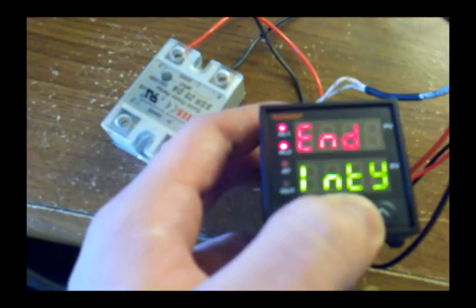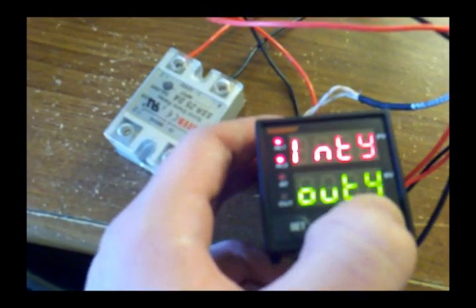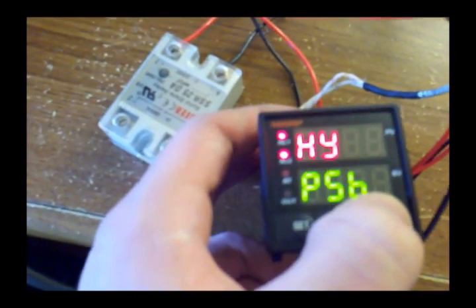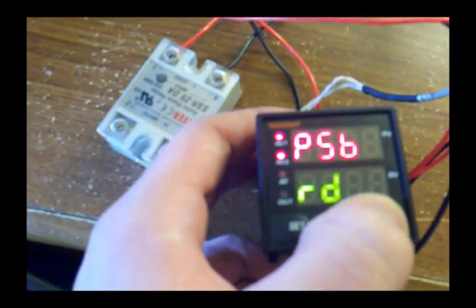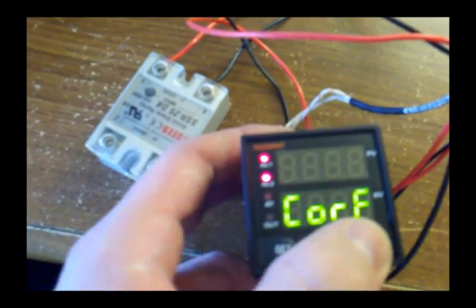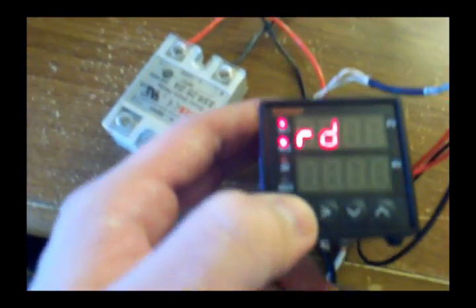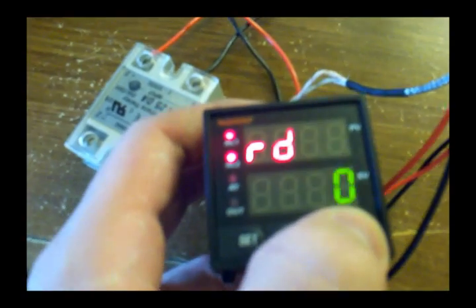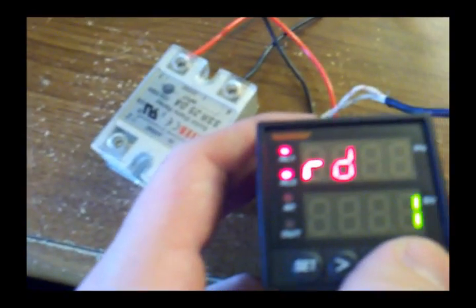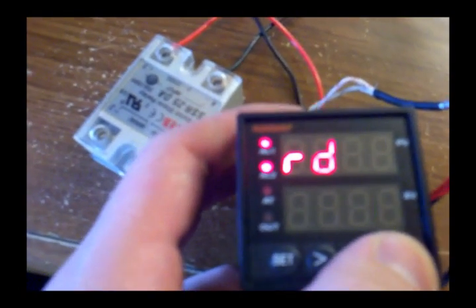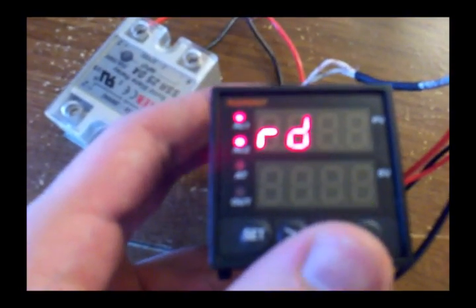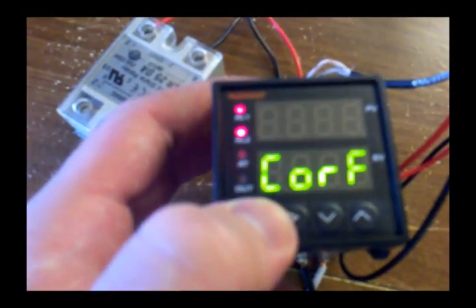You don't really need to mess with out. You don't need to mess with that. You do need to mess with R, D. R, D has two values, 0 and 1. If it's at 1, that means you're using this to cool stuff down. If it's set at 0, it means you're using this to heat stuff up. So I'm going to leave it at 0.